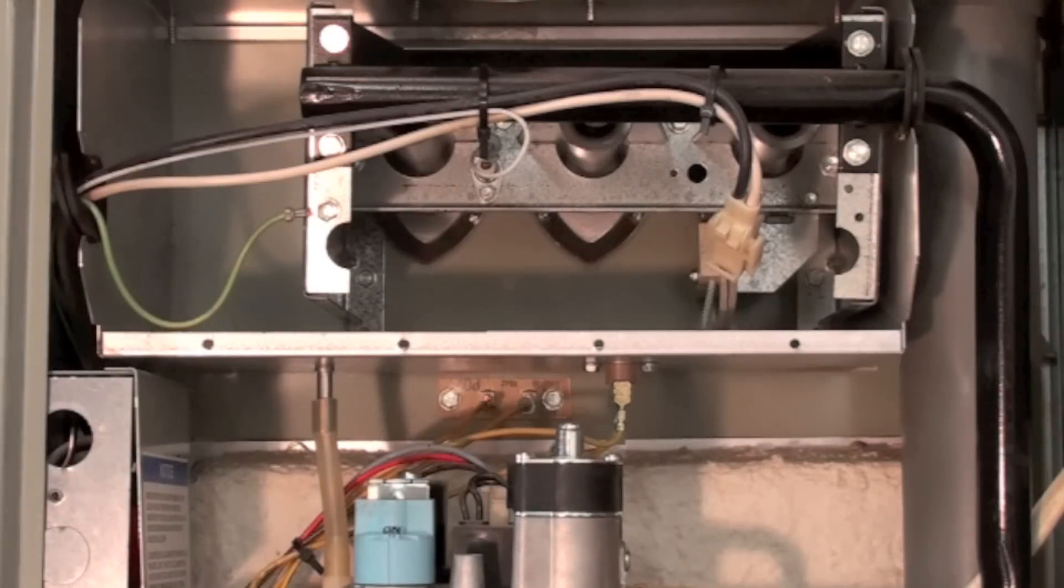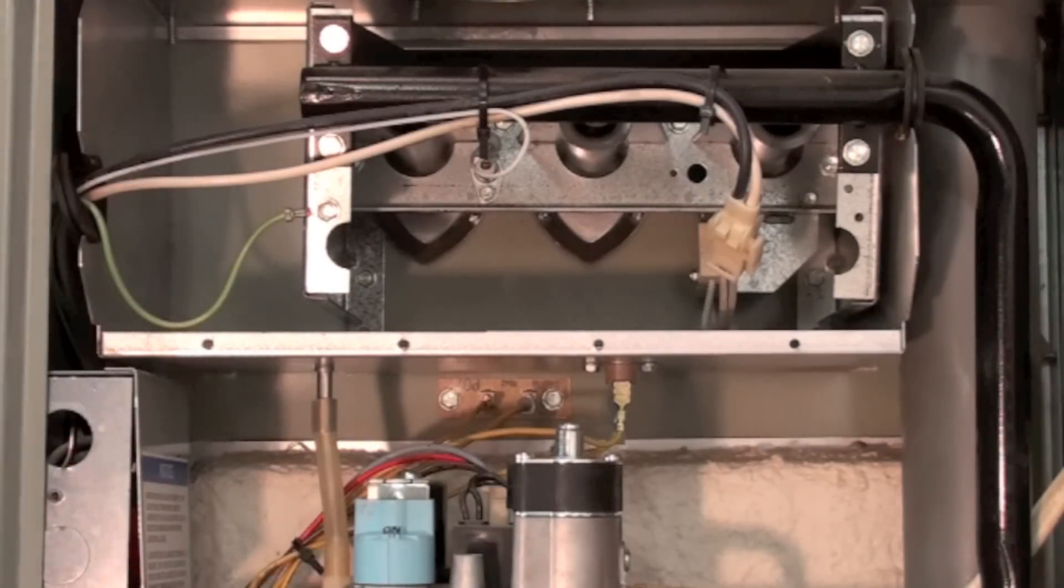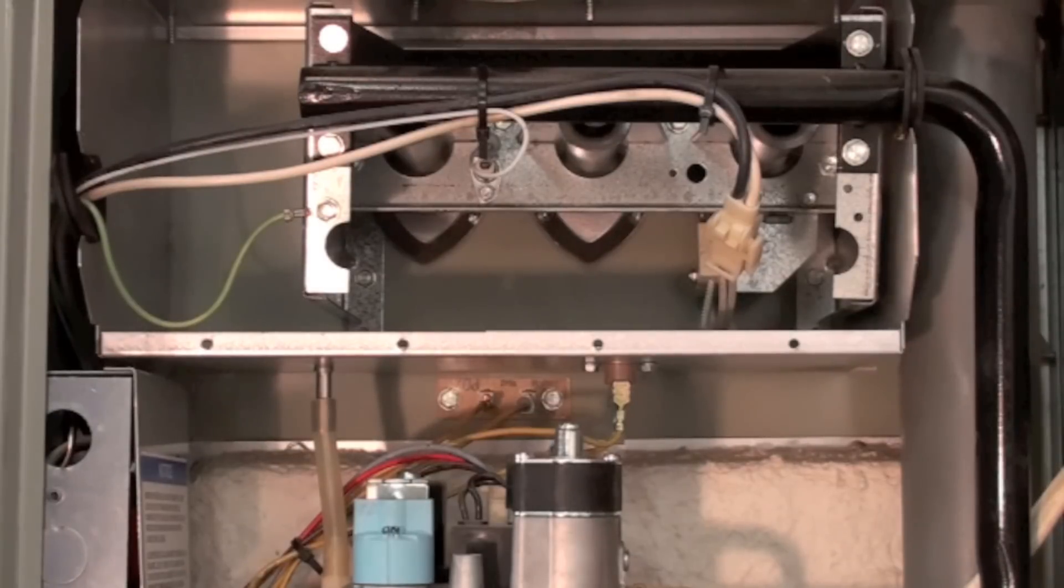That means if you have a short cycle it runs maybe four to seven seconds and shuts off. Burner comes on then shuts off. Burner comes on then shuts off. Or maybe it comes on and stays on for a while then shuts off and goes through this cycle.